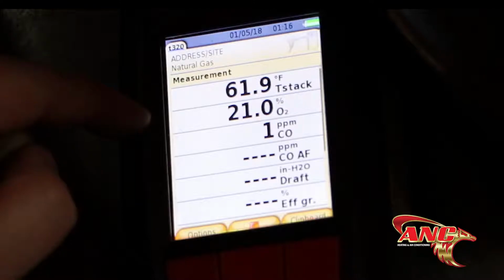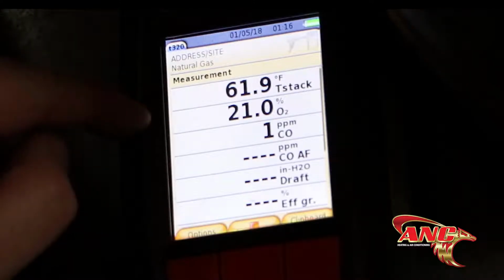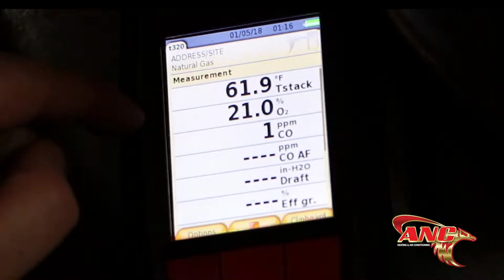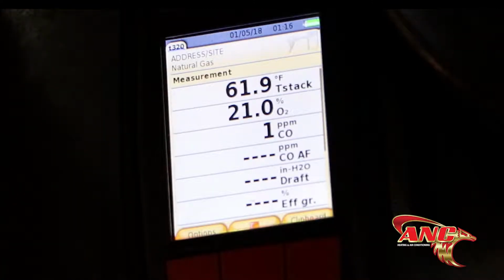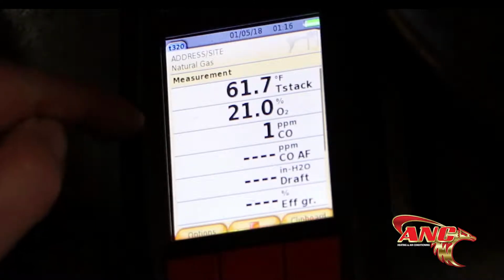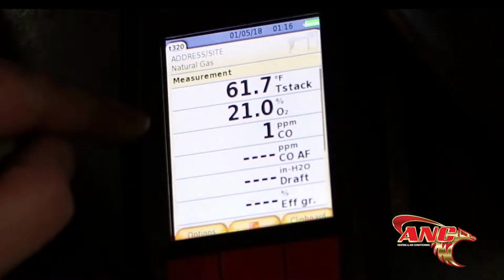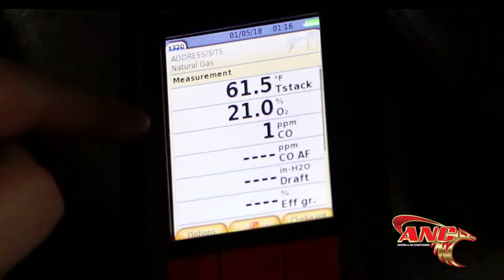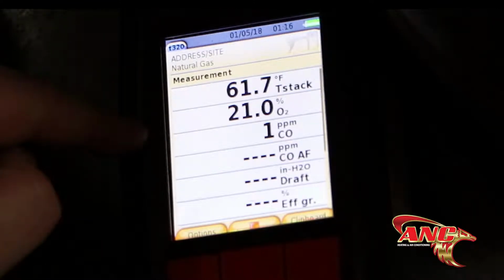And what we're looking for here is, after the blower kicks on, I don't want to see that number go up. The reason I don't want to see that go up, the fire is contained in an airtight chamber. And when that blower kicks on, if that oxygen level goes up, we know there's a crack in that heat exchanger. So we definitely don't want to see that.